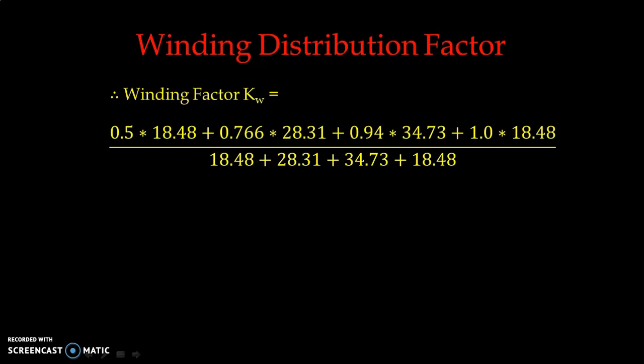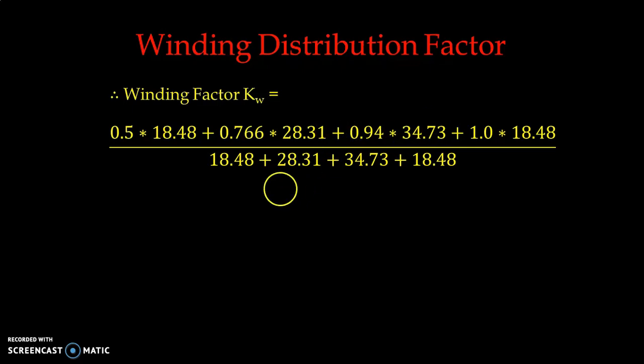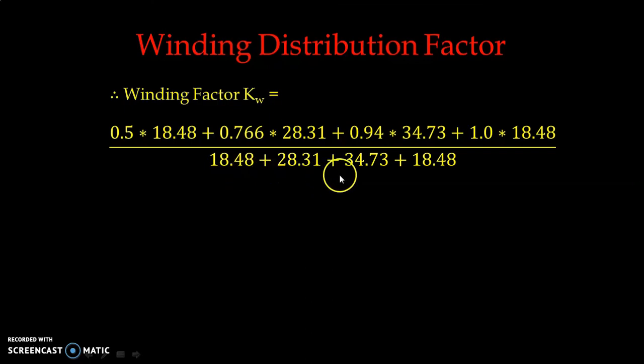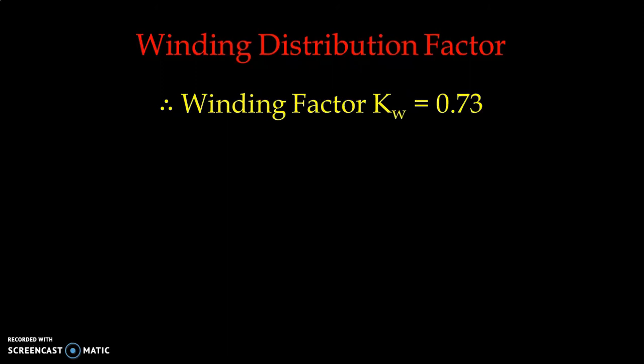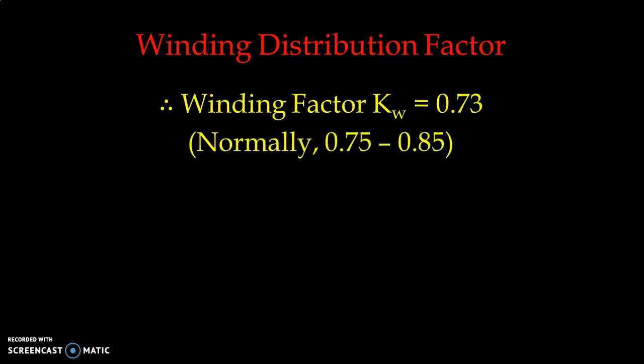Substituting the exact percentage values: (0.5 × 18.48 + 0.766 × 28.31 + 0.94 × 34.73 + 1 × 18.48) divided by (18.48 + 28.31 + 34.73 + 18.48). Simplifying, Kw = 0.73. Normally we take 0.75 to 0.85 in the case of single phase induction motor winding factor.